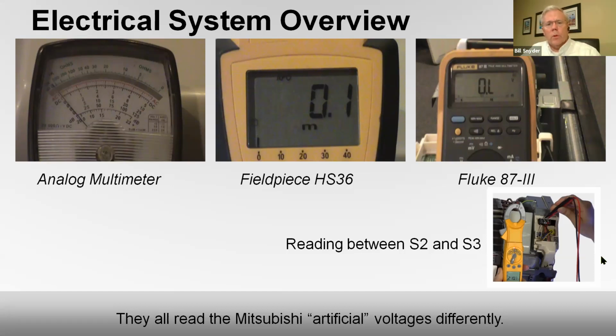And you can read that with meters similar to what's on the screen here. This happens to be an analog meter. Typically, that's what they used for many, many years. Back when I first got into business, that's basically all we had. We didn't have too many digital meters back then. But an analog meter is really easy to see this type of signal. You'll see the needle bouncing around as it's receiving the voltage that varies. I just recently bought an analog meter at a big box store. I paid around $10 for it. So they're not real expensive. You can get an expensive one, but it doesn't have to be.